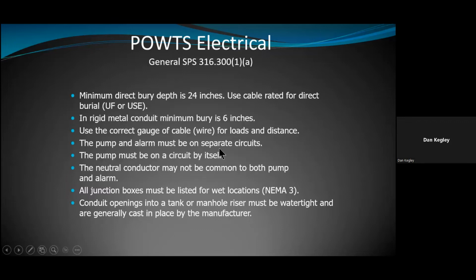The pump and alarm must be on separate circuits, so you can't put them on the same circuit breaker. So basically, you have to have two different circuit breakers, circuit power sources, so that if the pump kicks out the breaker, the alarm's still going to go off kind of thing. So the pump must be on its own circuit and the alarm itself must be on a separate circuit. Neutral conductors cannot be shared, so you can't run a multi-circuit wire out there for both the alarm and the pump.